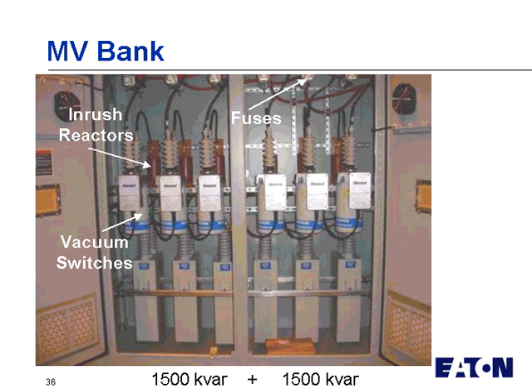Here's an example of one where we point out the bottom actually are the capacitors. There's 6 capacitors across the bottom, 500 kVAR per can. For a 3-phase system that makes 1500 kVAR on the left and 1500 kVAR on the right, and then you have fuses on the top, inrush reactors in the back, and vacuum switches in the front.